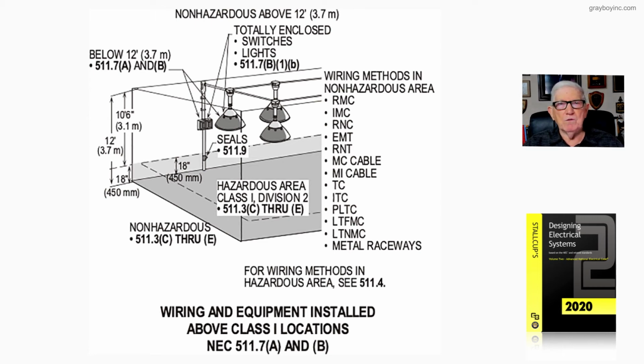I would review Table 4.4.2, and all those garage-type hazardous chemicals, gases, and vapors that could be there are listed in that table. And it will give you the upper and lower flammable limits. It'll give you the density of it. Does it settle in the 18-inch area or does it rise? All that will be listed there for your review. And notice that table contains it all. And then you just go to the chapters to do your classification.